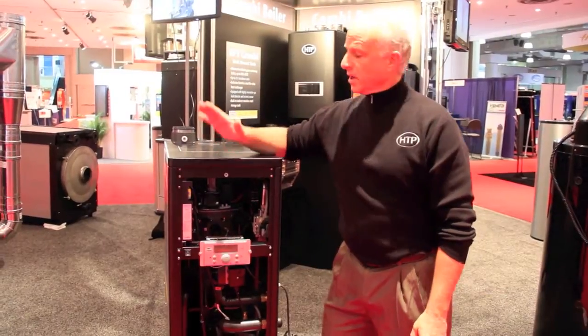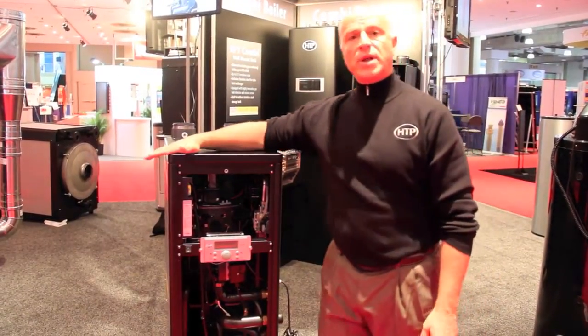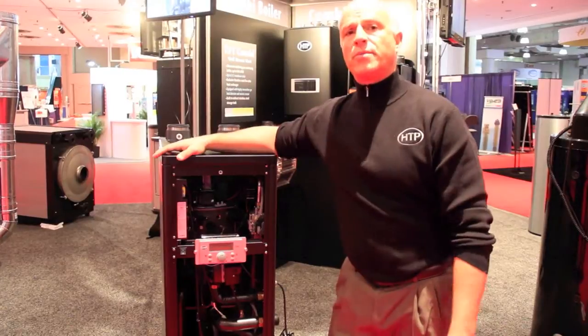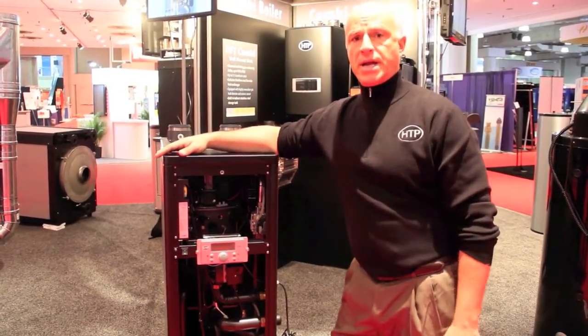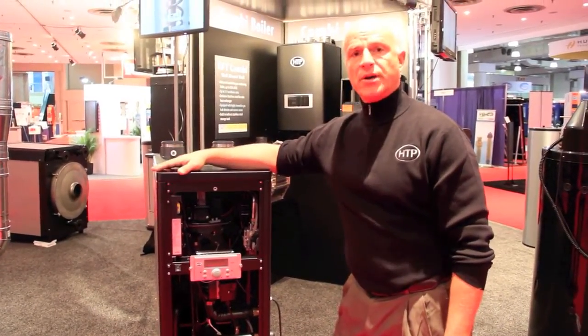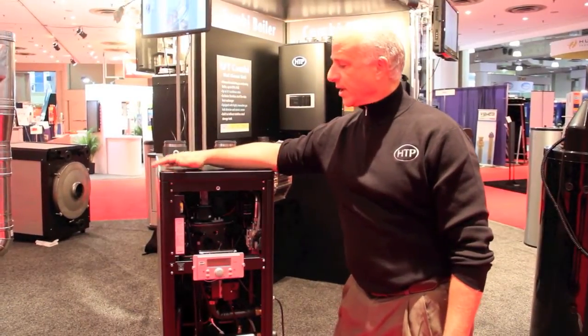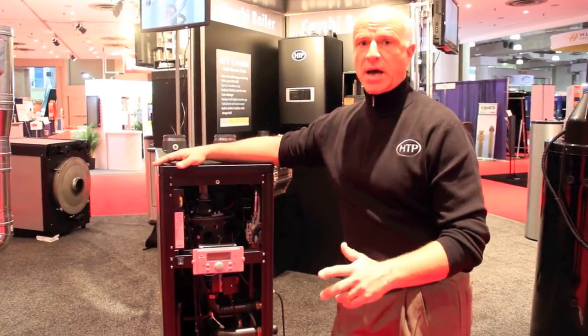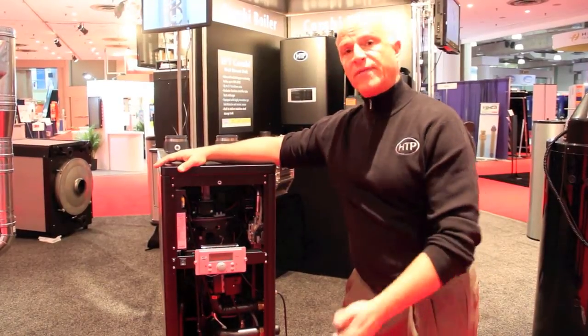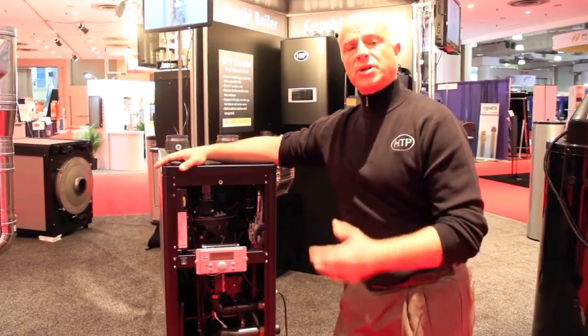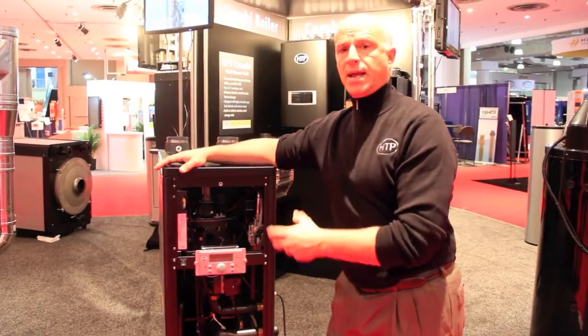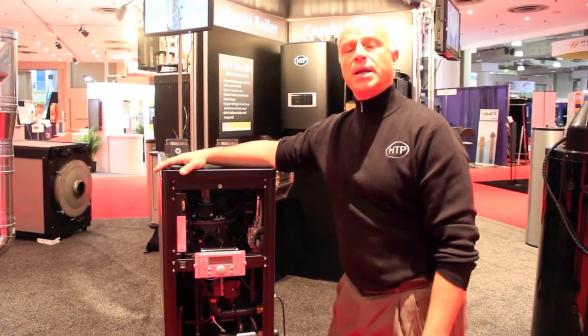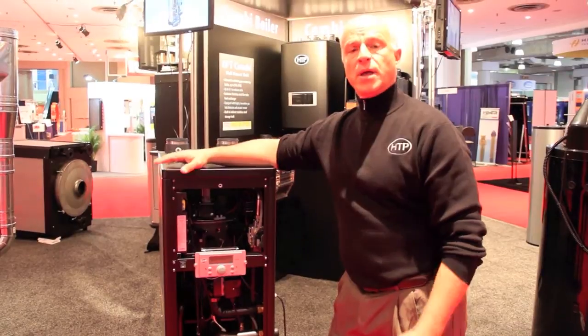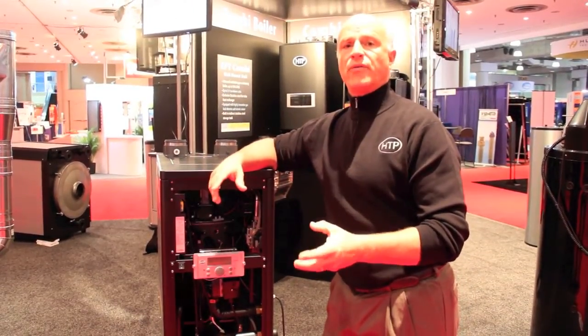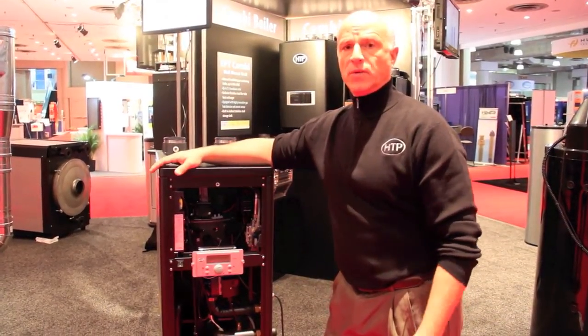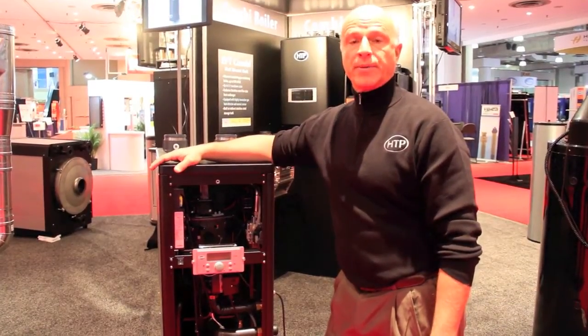I'm going to go over those, but this is our floor mount unit. It's 140,000 BTUs. We plan to come out with 2 other models, firing all the way up to 199,000, but right now we have this 140,000 BTU unit. Very compact design, it provides heating and hot water. We have an indirect tank built in where we're circulating the boiler water through that tank, and then we have a heat exchanger inside that transfers the energy from the boiler water into the coil very efficiently and rapidly to give you large amounts of hot water.